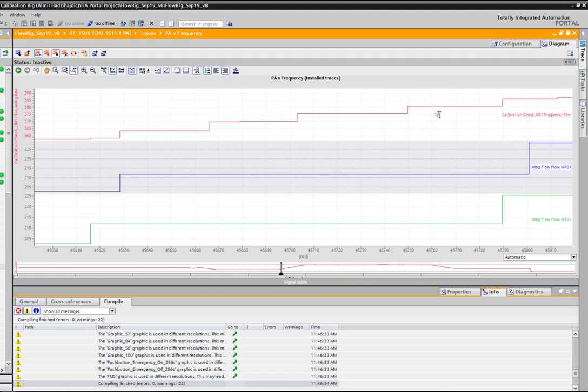It's not 100% conclusive. The high speed counter, before we even started this test we knew it was going to be faster than PROFIBUS PA but we just wanted to see how well PROFIBUS PA stood up. And with an update time of 10 hertz it's relatively fast and will cope with a vast amount of processes.